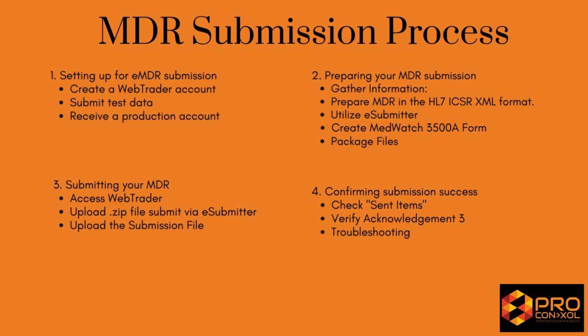There are 4 steps in MDR submission. First step is setting up for eMDR submission, which involves creating a WebTrader account, submission of test data, and receiving a production account.